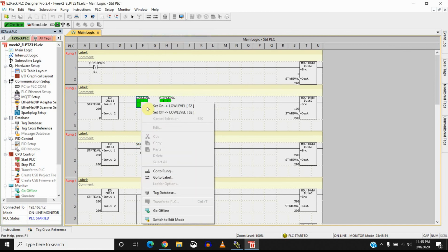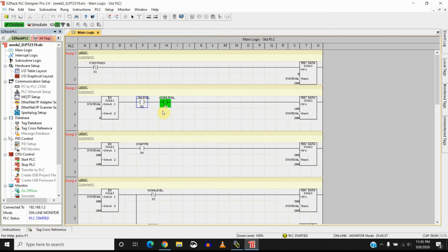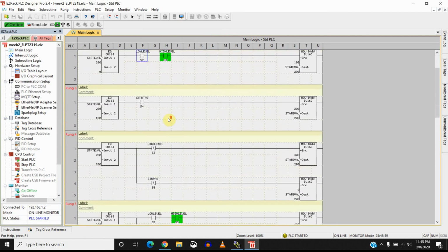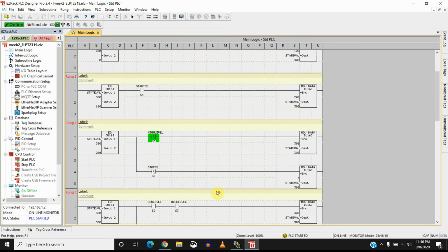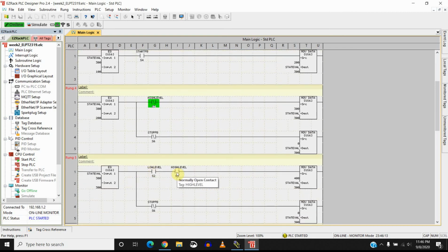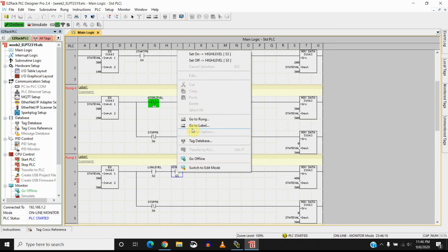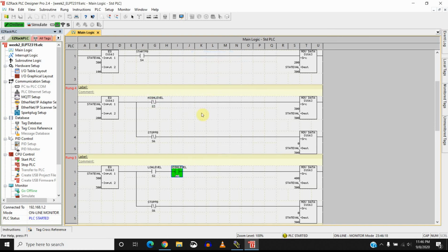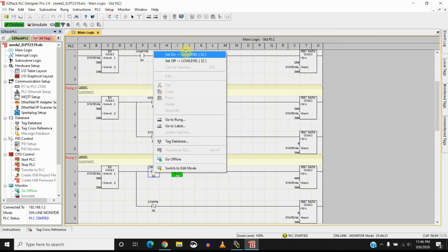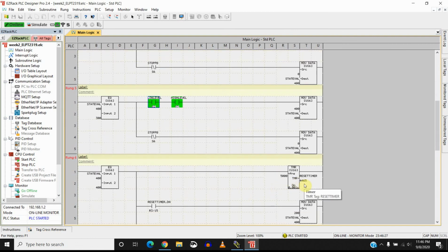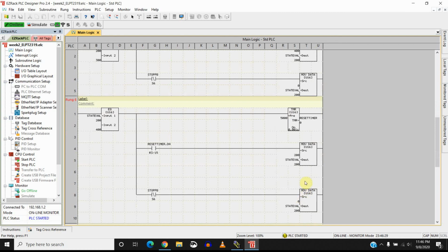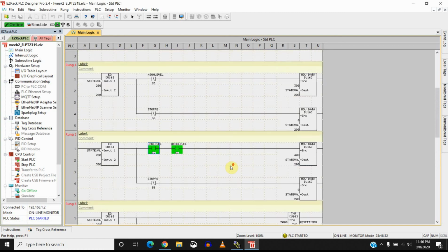Okay, so now the low level opens because it's not empty anymore. And pretty soon, it gets up to this point. I toggle the high level because it's full now, and I go to 300. Okay, so in 300, at some point I'll drain down the tank and I'll get the high level float. Then I'll get the low level float at some point, and I go to 400. At 400, my timer's running. And I went back to 200, which is where I want to be.